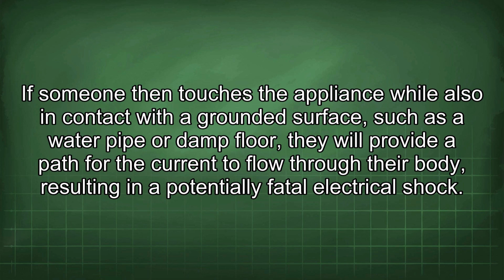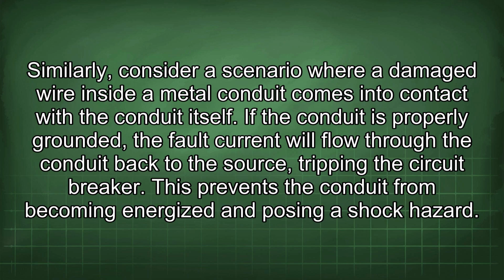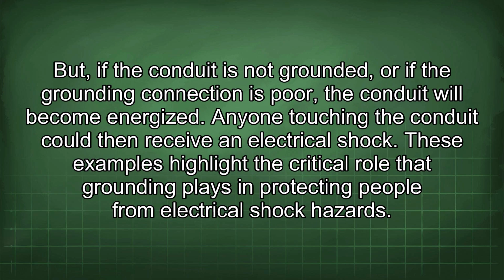electrical shock. Similarly, consider a scenario where a damaged wire inside a metal conduit comes into contact with the conduit itself. If the conduit is properly grounded, the fault current will flow through the conduit back to the source, tripping the circuit breaker. This prevents the conduit from becoming energized and posing a shock hazard. But if the conduit is not grounded, or if the grounding connection is poor, the conduit will become energized. Anyone touching the conduit could then receive an electrical shock.